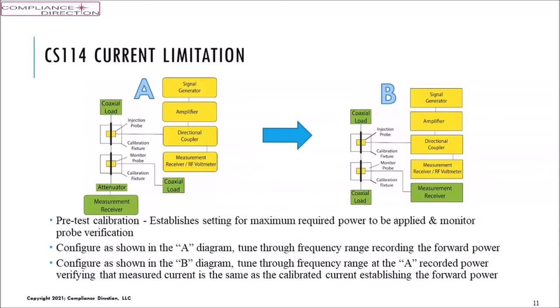That's a minimum. We also bring into being section B of this calibration, where now we move the measurement receiver to the monitoring probe. We play back the signal generator settings that we used during part A of the calibration, and we measure the current to see that it follows the calibration current limit line that we use to get our maximum levels. Now, this is a checking of the monitoring probe. The concept was that it's a more thorough all frequency type calibration check. So this was added to 461G because of the passive devices exemption clause. So this is a much more thorough area.